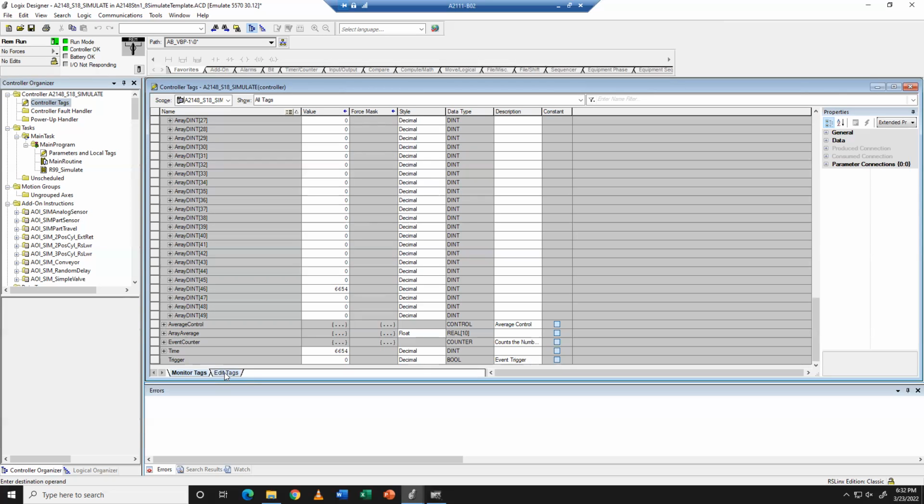Well, in the SLC world, or even the PLC 5s where everything's register based, you could use a counter and indirectly address a portion of your registers, so that on the first count, it will do all of device 1, increment up, do all of device 2, so that you could approximate what is done using the fancy add-on instructions.